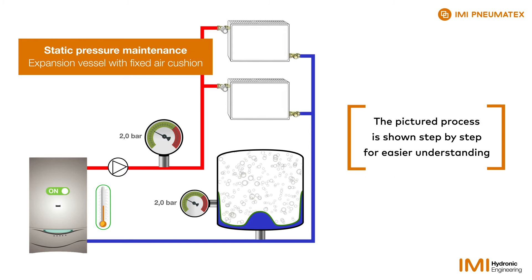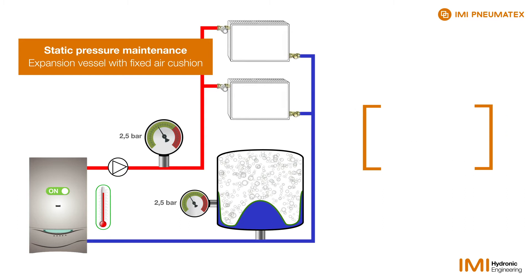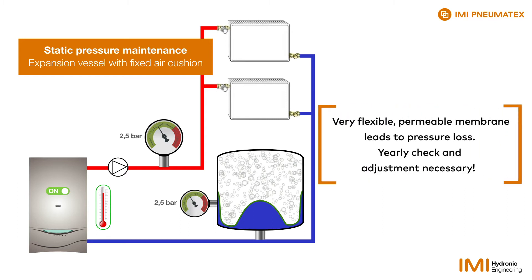If the system temperature continues to rise, the pressure also increases and the membrane continues to deform, allowing the heating water to flow into the vessel. The membrane must be extremely elastic, which results in a partial gas permeability known as loss of pre-pressure.